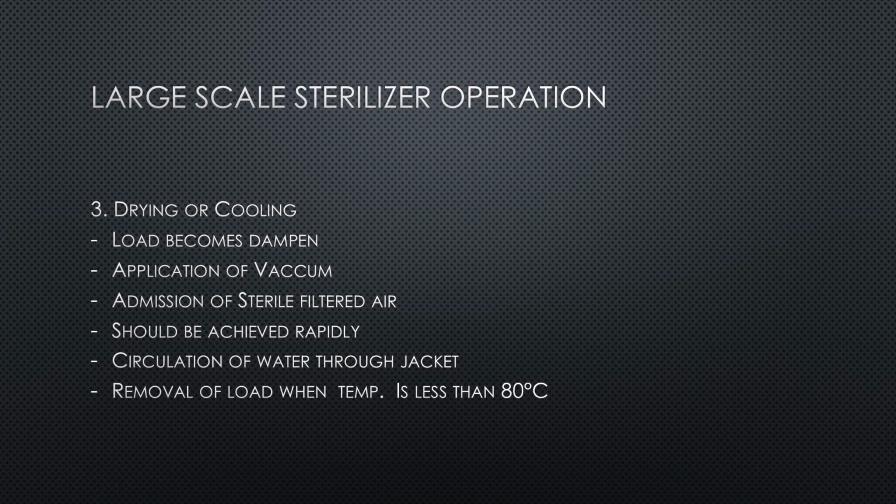The first step is air removal. Then the second step is holding that particular pressure or steam inside, that is heating up and exposure. And the third step is drying or cooling: after sterilization, whatever material has been dampened or become wet, drying of the material is equally important, and we have to achieve cooling of the material as well, not only drying but also cooling.